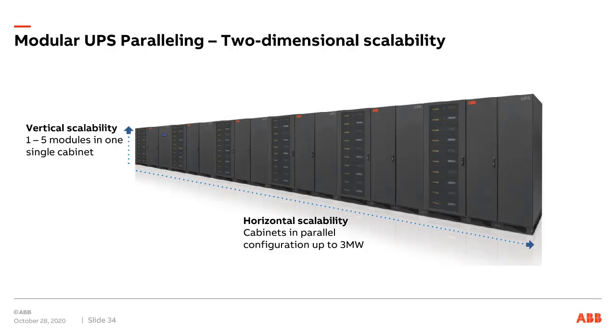The other thing, and what a couple of colos have brought up to me as a benefit, is that with a modular design like this, if you deploy your campus with modular UPSs as a colo, of course you want to rent your space, you want customers in there all the time, but sometimes they leave and go somewhere else, and sometimes you don't need the full power everywhere on your campus all the time. This adds the flexibility that you can move power modules around from UPS to UPS. So you can move capacity from one part of your data center to another. If you have excess capacity or more power modules than needed in one UPS or one group of UPSs, you can move some to another UPS if there's space.